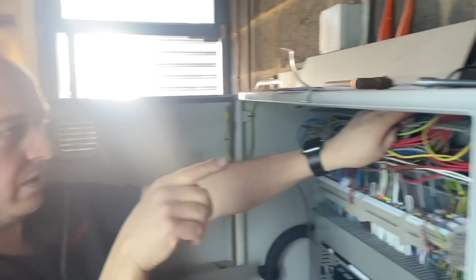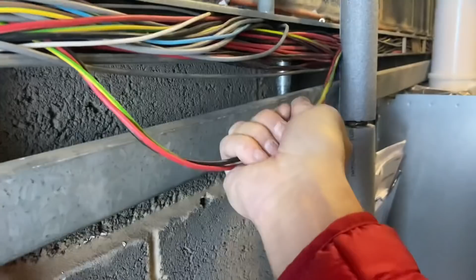Now what I'm trying to do is fish out the secondary return pump on the domestic hot water and find out the live feeds. We haven't got any drawings, we haven't got any labels other than numbers. Some things are labelled up in the fuse spurs, but not everything, and we can't find where the secondary hot water is. So we now just need to find the live and neutral and the earth incoming. Have all that. So basically what we're doing is pulling one, like this one, pulling it and following it and seeing where it goes.